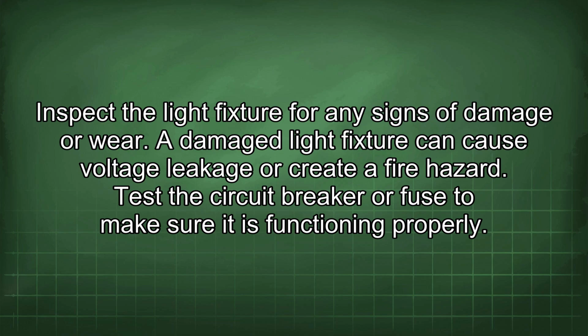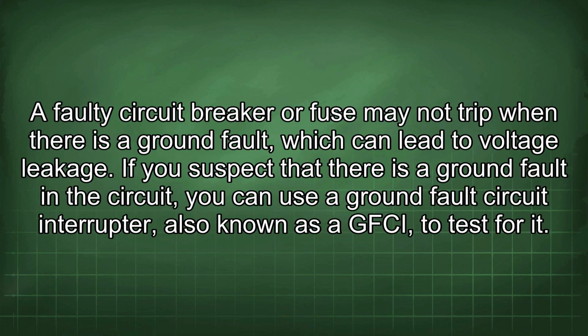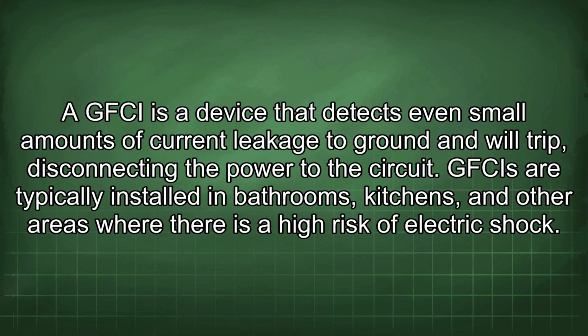Test the circuit breaker or fuse to make sure it is functioning properly. A faulty circuit breaker or fuse may not trip when there is a ground fault, which can lead to voltage leakage. If you suspect that there is a ground fault in the circuit, you can use a ground fault circuit interrupter, also known as a GFCI, to test for it. A GFCI is a device that detects even small amounts of current leakage to ground and will trip, disconnecting the power to the circuit.